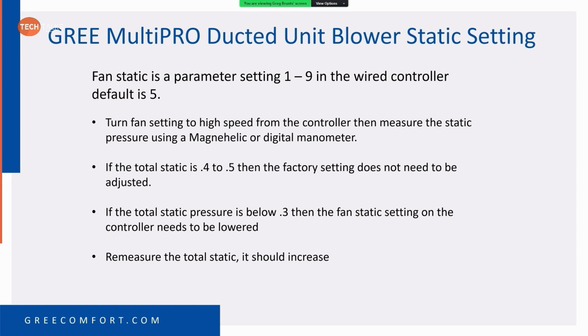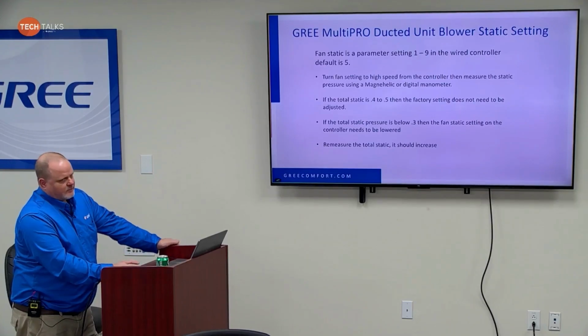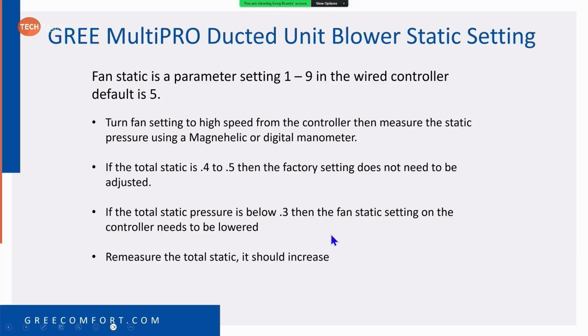If your total static pressure is 0.4 to 0.5, then that factory setting of 5 is perfect. If the total static pressure is 0.3 or below, you're probably going to need to lower that, so you might try more like 3 or 4. Depending on how dramatic a change you make, if you go from 5 all the way down to 1, you should see a pretty significant difference in your static pressure. If I go from 5 to 4, you're not going to see as much. But when you're lowering that curve, your static pressure should drop.